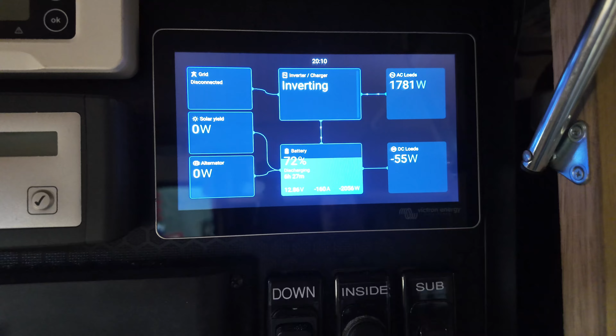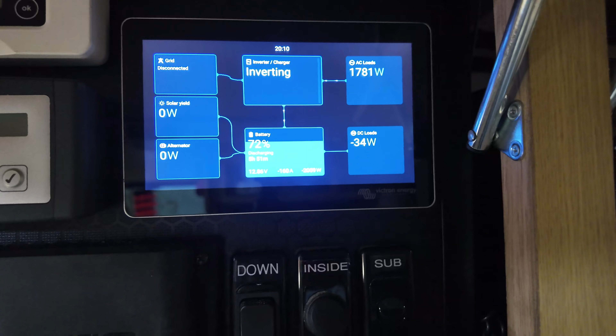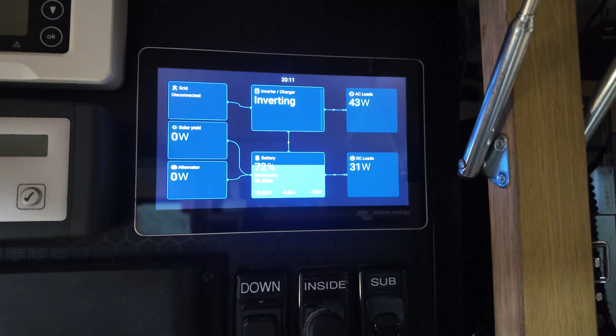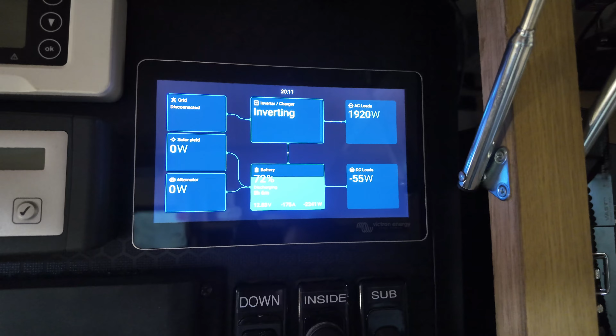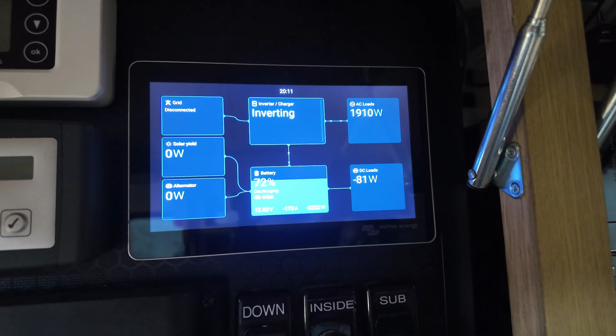The sandwich press is pulling 160 amps off the batteries, 1800 watts in AC power. Aircon is fully off now, so we can see just the sandwich press is pulling very close to 150 amps. I'm going to turn the sandwich press off here and hit my kettle. The kettle is going to pull more power because it's a bigger power consumer, and it's pulling very close to 180 amps.